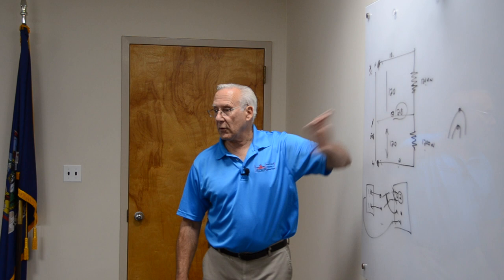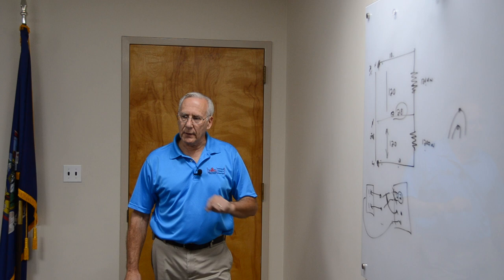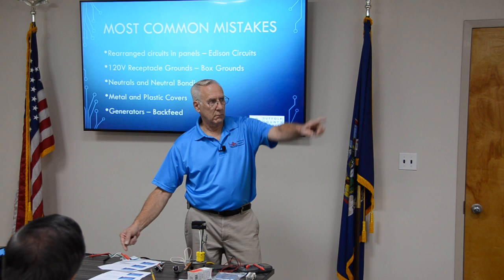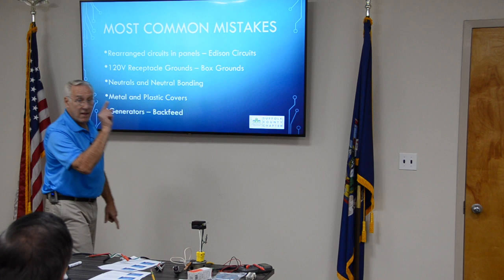They were wired correctly in there when the school was built. And then years later, everybody messed up the panels. I've seen it so many times. I've seen these wires burn, overheating with this. Okay, so that's the most common mistake. That's one of them. Box grounds.